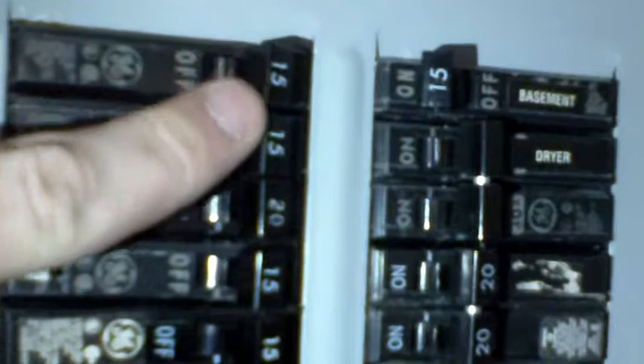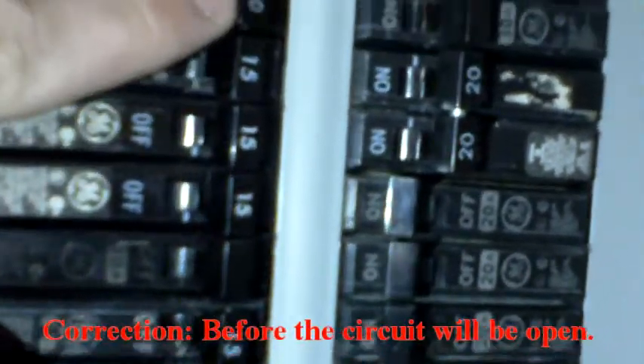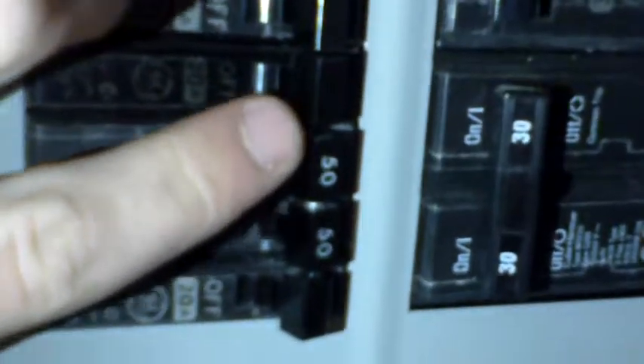Now look, at the end of the switch there is a number. Can you read it on the camera? Alright, we're good. This represents the number of amps that can flow through the circuit before the circuit will be open. Most use either 15 or 20 amps, but if you look down here, you'll see a larger number, 50 or 30, on this side.